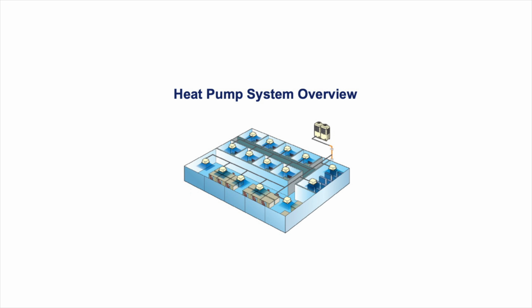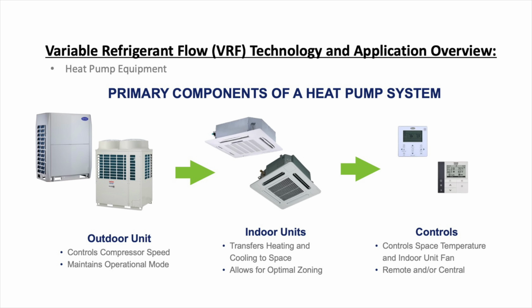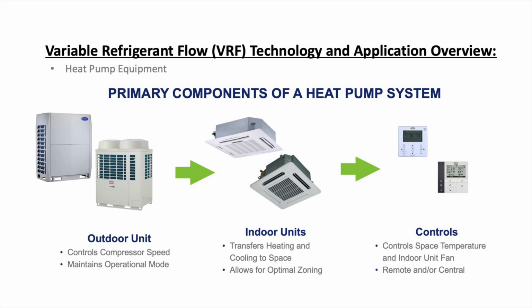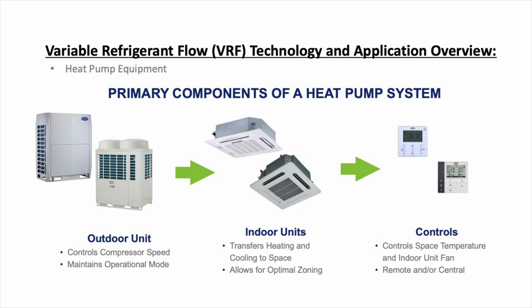Let's look at the different components of a heat pump system. You have your outdoor unit, which controls the compressor speed, and it maintains the operational mode. So this is what tells the entire system to be either in heating or cooling. You have your indoor units, which transfer the hot air or the cold air to the space. And this is what allows for optimal zoning because you can use individual indoor units at each zone. And you also have your controls, your thermostat or remote controller, which gives the end user control of their indoor unit.